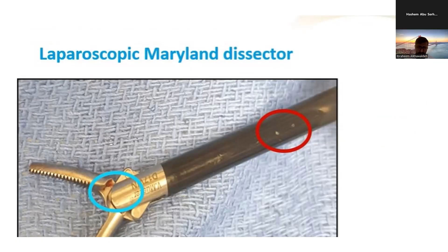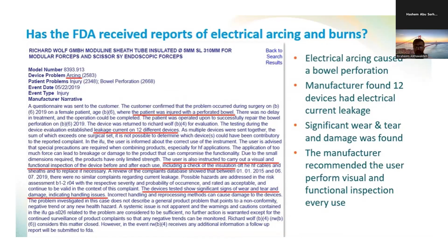And in this report, after research, there was an electrical arcing caused bowel perforation, and 12 devices had electrical current leakage; significant wear and tear damage was found. The manufacturer recommended after that all users should perform a visual and functional inspection with every use, and they provided the kit or tool for it, as we will see in a bit.